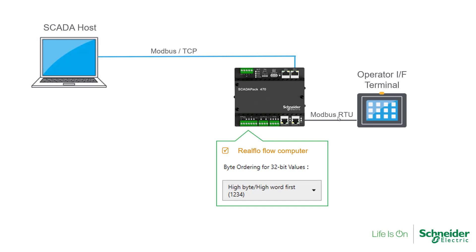you will need to change the 32-bit byte order to 1234 on any Modbus devices that are already polling your SCADAPack.